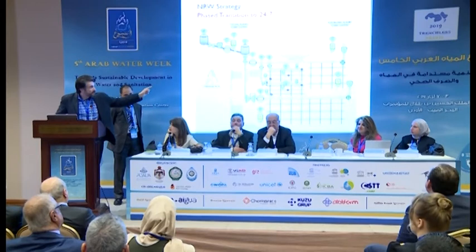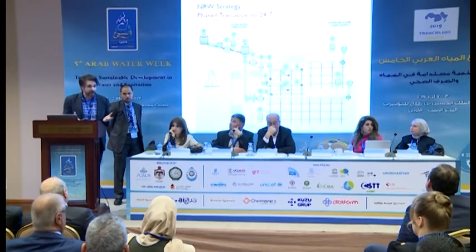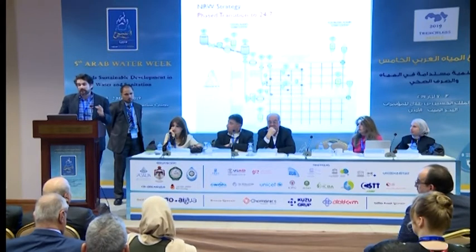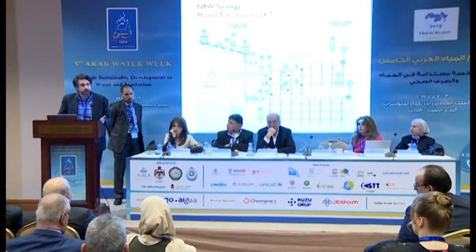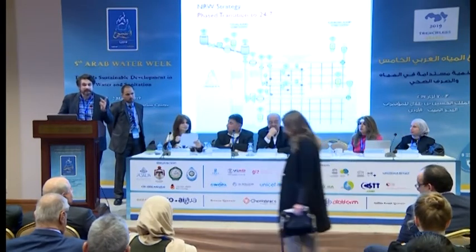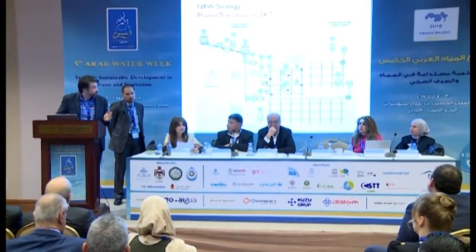And each one has a specific design criteria. Many of these donor projects make the work, they install the equipment, but the utility cannot report what is my minimum night flow, what is my average zone pressure. Because they cannot report, we cannot consider them as having passed. So it takes infrastructure work, it takes operation, and it takes telemetry, reporting, monitoring, and the whole deal.